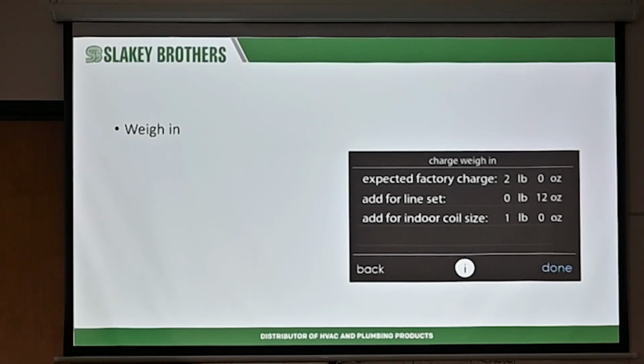Okay? Again, this is just some numbers of what it's talking about when you're weighing it in. The factory charge, how much you're adding. Now notice that this was nice. This is what you add for the line set. It says 12 ounces for the line set. But because of the high efficient indoor coil, it's saying to add 1 more pound to it.